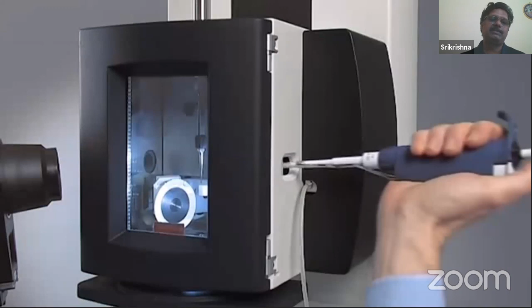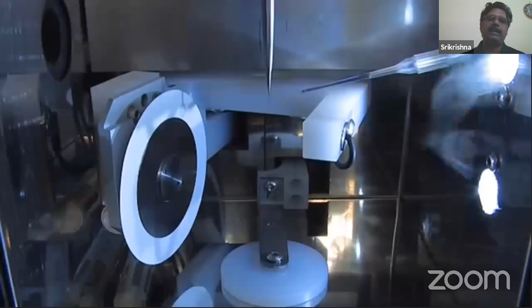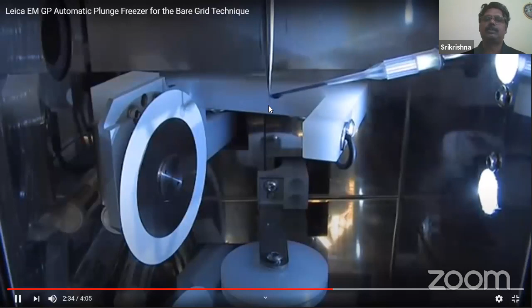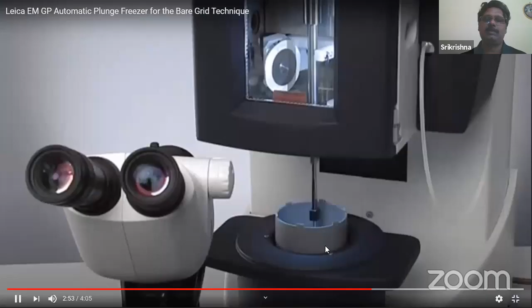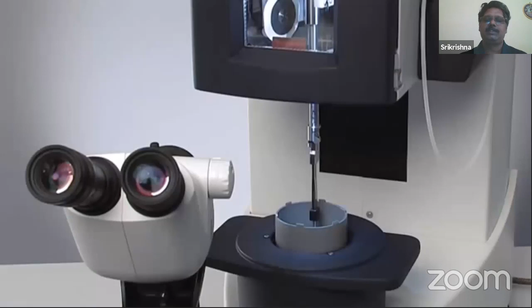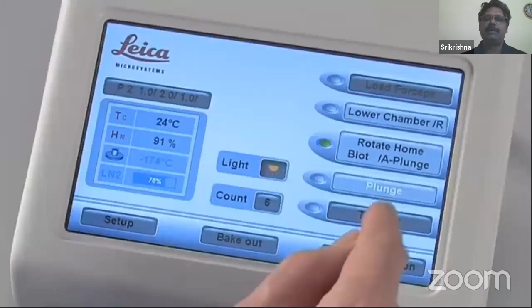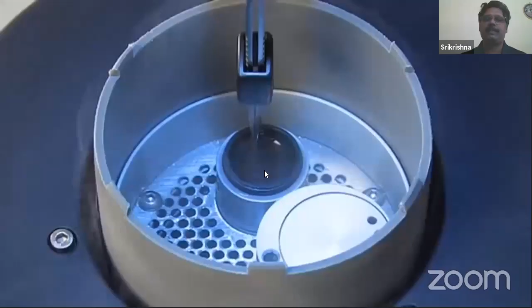So now the protein sample is being applied onto the grid here. Then blotting is initiated. Excess fluid will be absorbed by blotting paper. It is immediately plunge frozen into the liquid nitrogen. This is called the plunge freezing sample preparation technique. So now the sample is rapidly frozen into liquid ethane, which is maintained at liquid nitrogen temperature. And henceforth, the sample has to be at liquid nitrogen temperature, so minus 185, till you image.